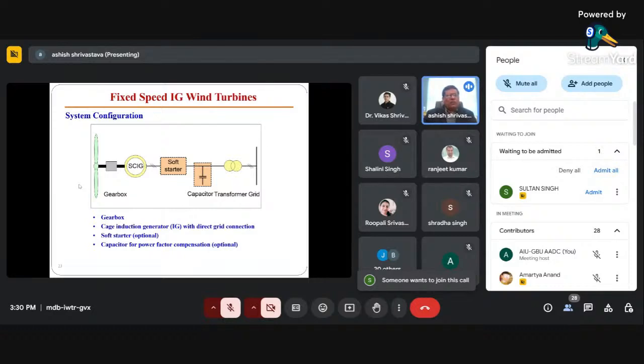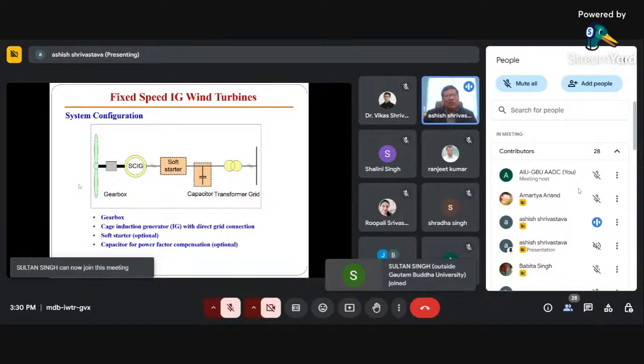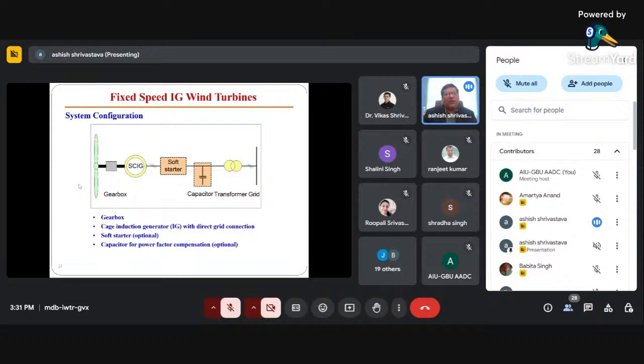Once we are talking about the fixed speed, then we have a gearbox, then a squirrel cage induction generator, then a soft starter, then a capacitor which ensures the power factor, that is reactive power compensation, then a transformer, then the grid. So the power flow is unidirectional, from the windmill to the grid. In the case of DFIG, we can have a bidirectional power flow. That is also an advantage. That's why DFIG is gaining popularity these days.